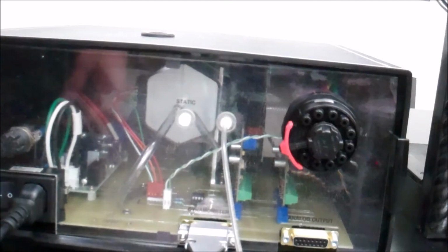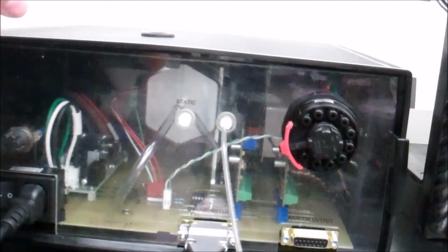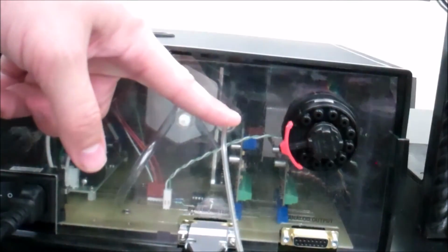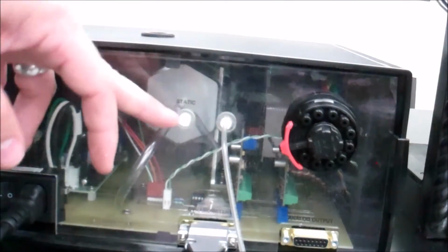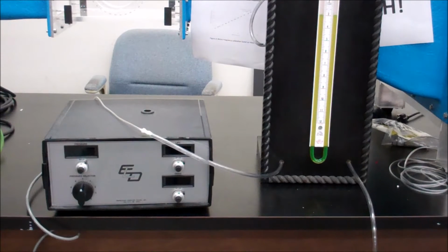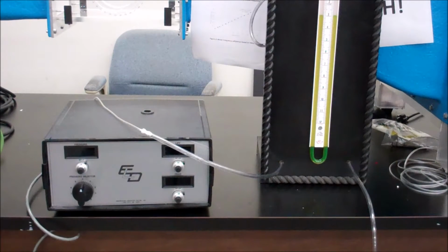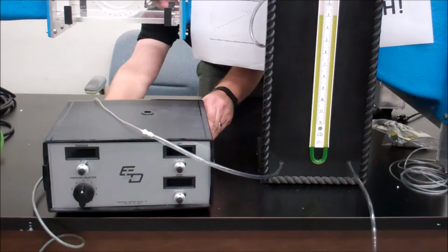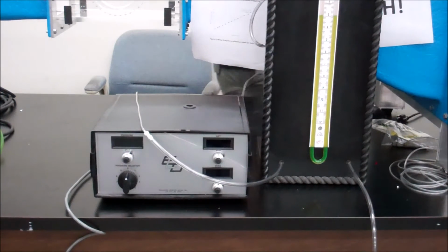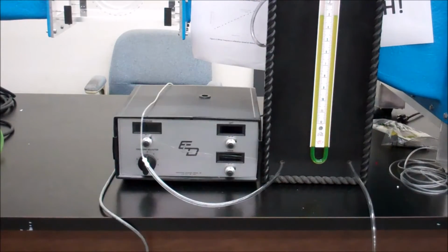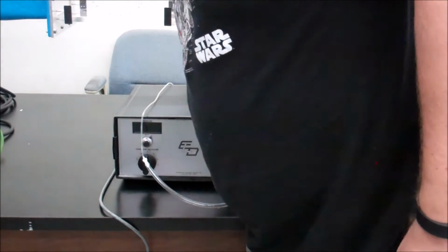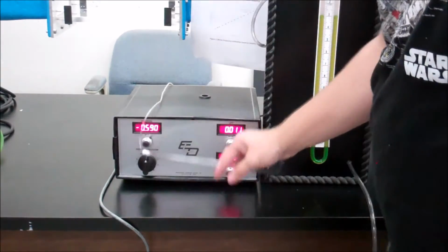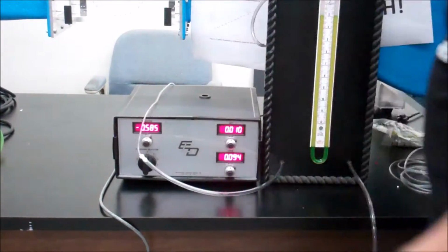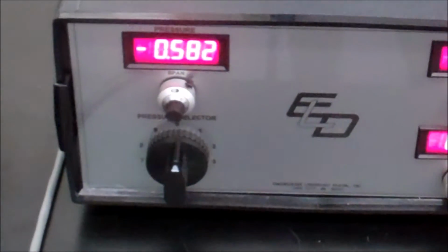Now, once you've connected it the way you want it, for calibration you connect the total port to the manometer and leave the static port open. So you're going to go ahead and turn the digital pressure transducer around and plug it into the power outlet. Be careful not to trip over the wire when you plug it in. Then you turn the switch on the back by the power cable, and you notice that it turns on. You can see here on the left the voltage at 0.